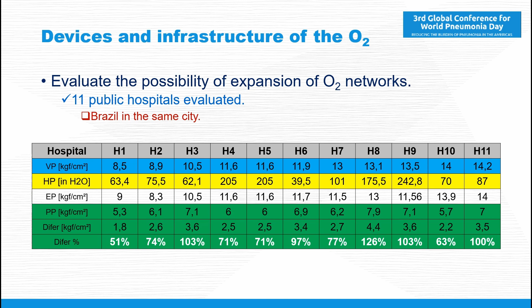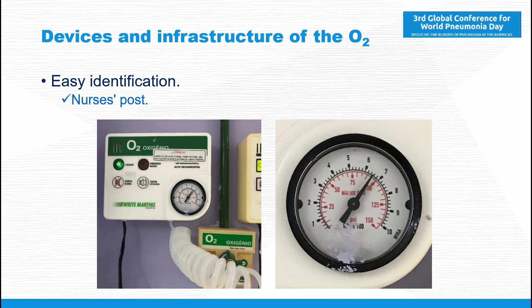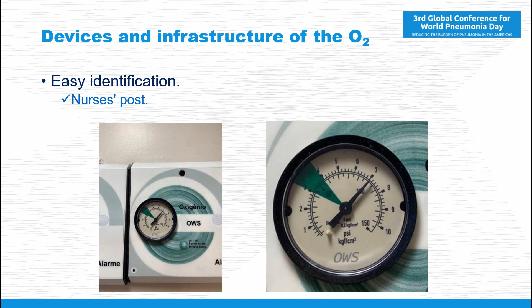Imagine the amount of oxygen that is being lost because of this. Because when you adjust, for example, 5 liters per minute in a flow meter, this information will not be true. So healthcare professionals use more oxygen than the patient needs. It's easy to identify this. Just go to the nurse station and look at the pipeline pressure. If it's right, no problem, it's good. If it's higher than necessary, you must reduce the pipeline pressure.